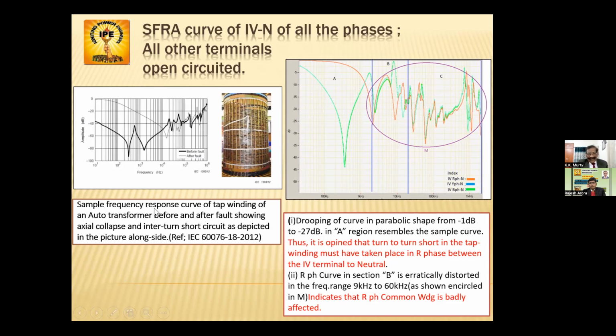Sample frequency response curve of tap winding of an auto transformer before and after fault, showing axial collapse and interturn short circuit is depicted in the picture alongside. This is the picture. So the curve what we got resembles this. You can see this resemblance. See, it is coming like this. So it is resembling the same way. Yes, you can see this.